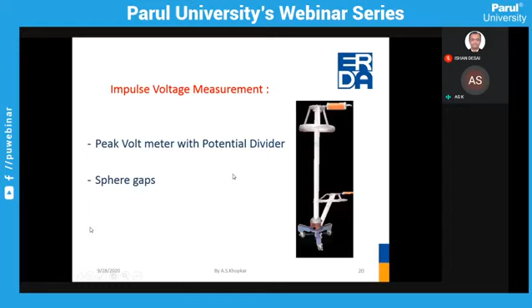Now let me tell you about some of the high voltage testing which we carry out in the laboratory. High voltage testing, as I said, is basically the testing of the insulating media, and that's why people normally call it a dielectric test also, because we check the dielectric property of the insulation. The other name of high voltage testing is the dielectric test. Basically in the laboratory we do this to check the withstand capability of the insulation against TOV, temporary overvoltages, LI, lightning impulse voltages, and SI, switching impulse voltages.